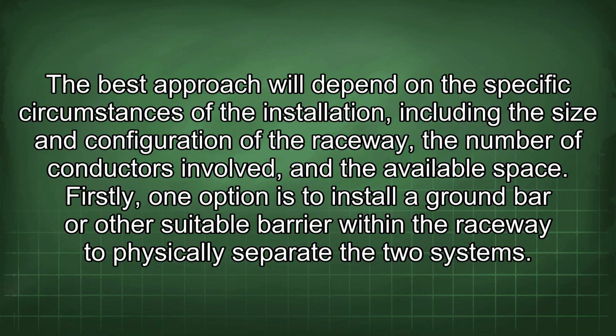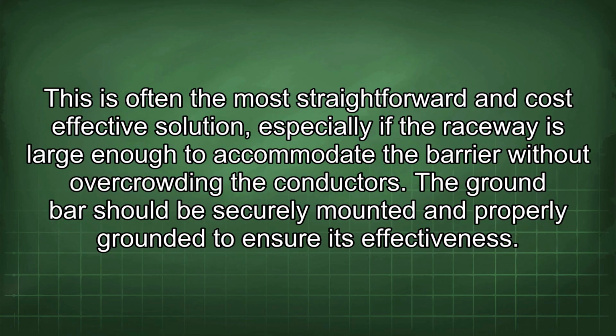Firstly, one option is to install a ground bar or other suitable barrier within the raceway to physically separate the two systems. This is often the most straightforward and cost-effective solution, especially if the raceway is large enough to accommodate the barrier without overcrowding the conductors. The ground bar should be securely mounted and properly grounded to ensure its effectiveness.